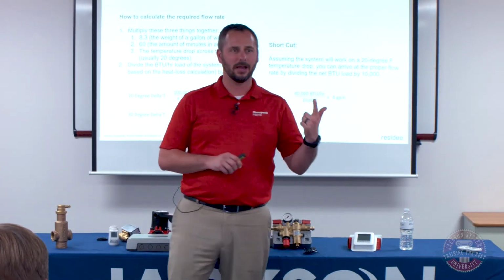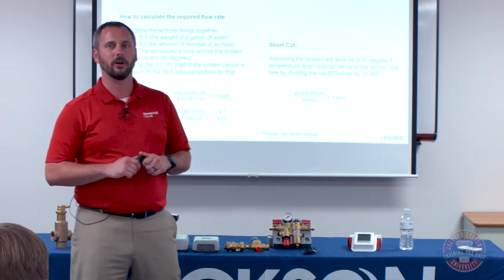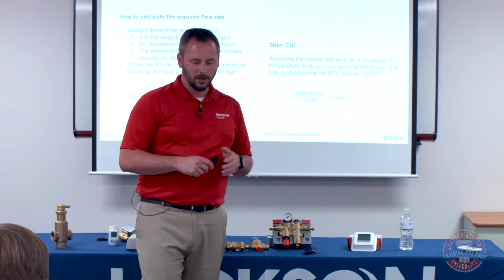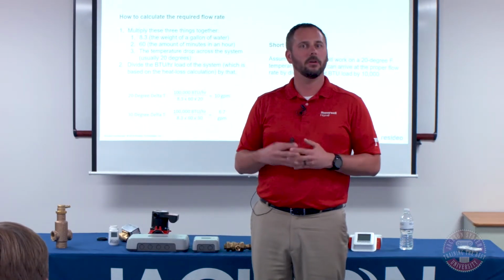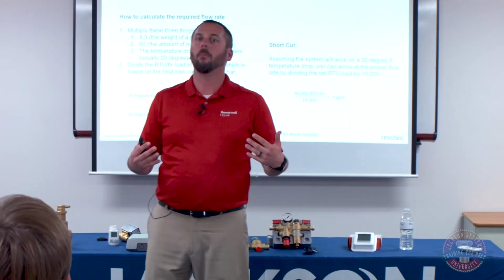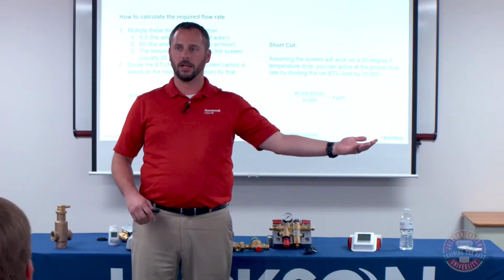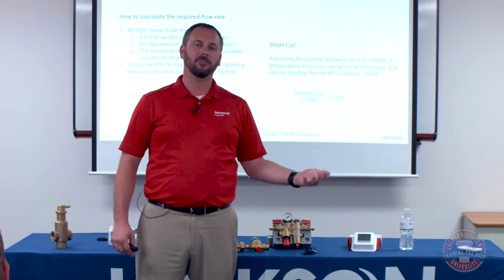That's our 20-degree delta T. So when you take 8.3 times 60 times 20, it's 10,000. So if you've got a 100,000 BTU boiler output, 10 gallons a minute. In this example, 40,000 BTU output divided by 10,000, 4 gallons a minute. So you can immediately walk up to a system now. You can look at the output rating on the boiler, assuming it was sized properly, and look at the max capacity that boiler should ever need for flow rate.